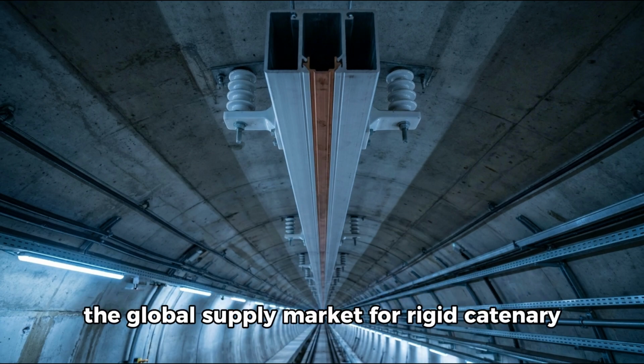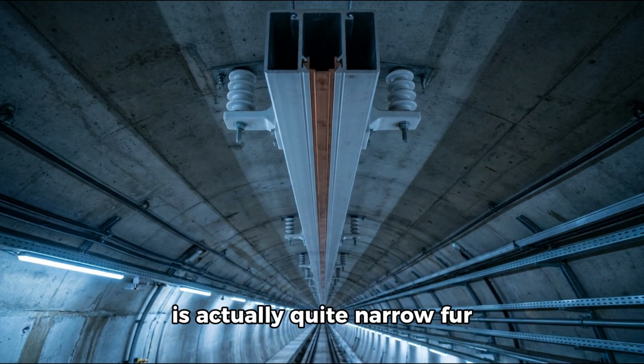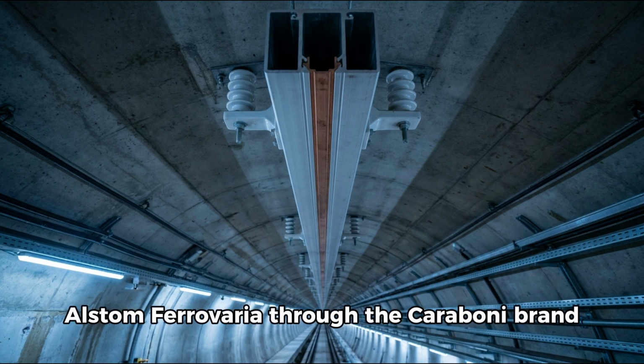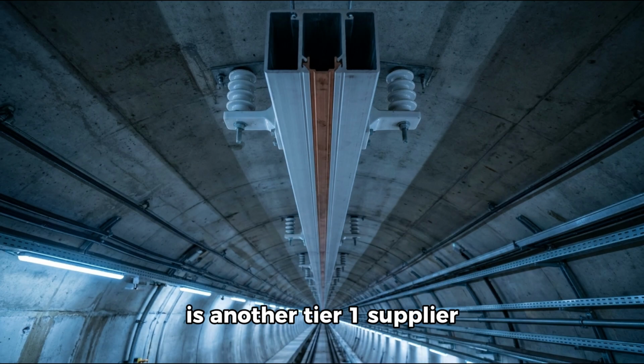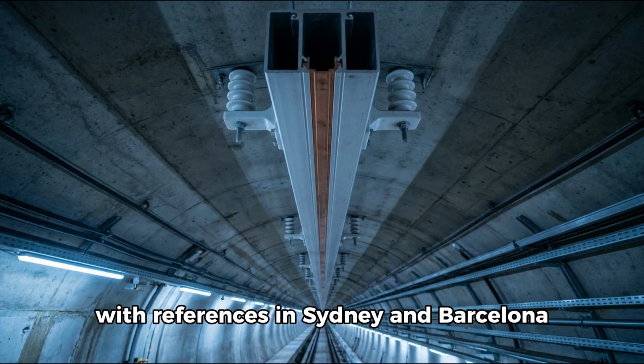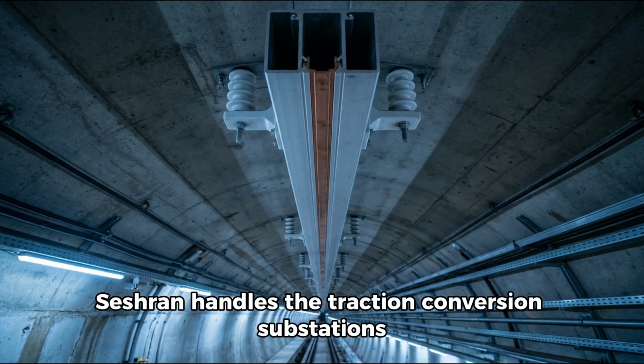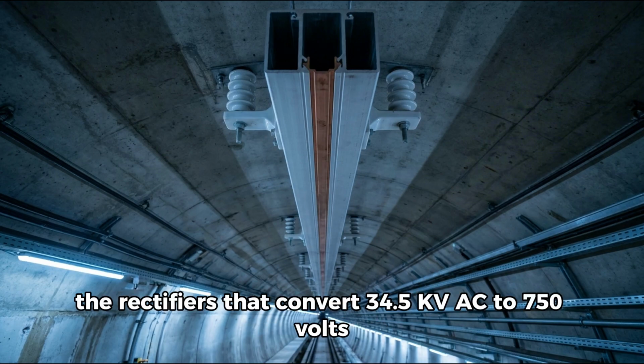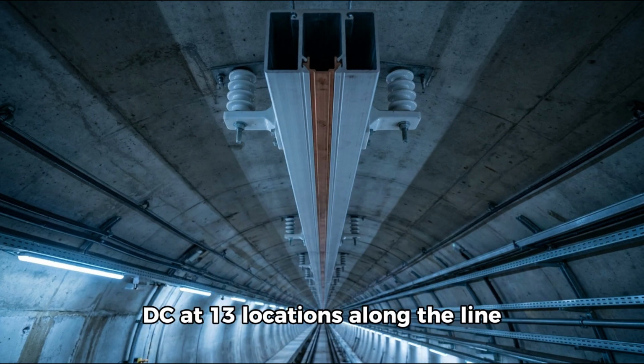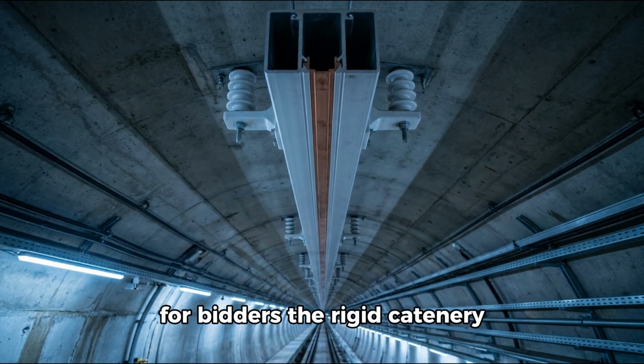The global supply market for rigid catenary is actually quite narrow. Furrer+Frey of Switzerland is arguably the world reference. Alstom Ferroviaria, through the Caraboni brand, is another Tier 1 supplier, with references in Sydney and Barcelona. Secheron handles the traction conversion substations, the rectifiers that convert 34.5 kV AC to 750 volts DC at 13 locations along the line.